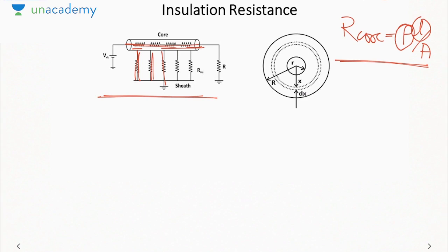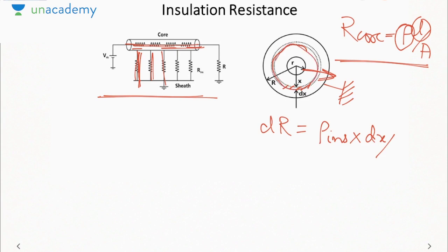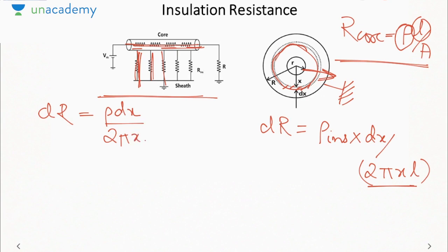But what about the insulator? Here I have shown the cross-sectional view of a cable. Up to small r we have our conductor, and up to capital R we have our insulation. So we consider a small filament inside the insulating layer which has a radius x and a width dx. Now the current flows from the core to the earth. We will consider this as earth, so current will flow radially outwards. The length that it encounters while flowing radially outwards is dx. So the small resistance will be rho insulator into dx, and the area that it encounters is the curved surface area of this cylinder, which is 2 pi x into L. So dR is rho dx by 2 pi xL. Remember, here rho is the insulator resistivity, whereas earlier rho was the core resistivity.